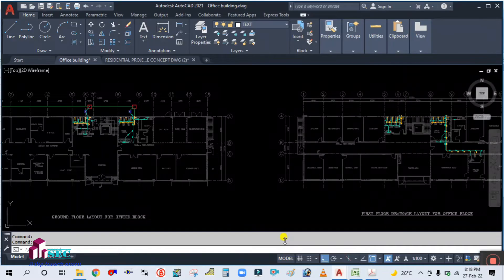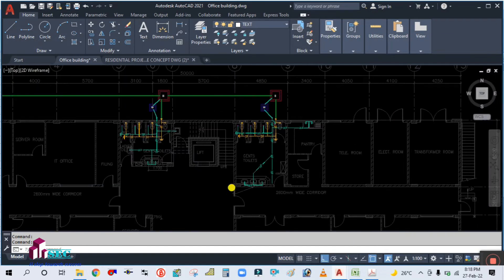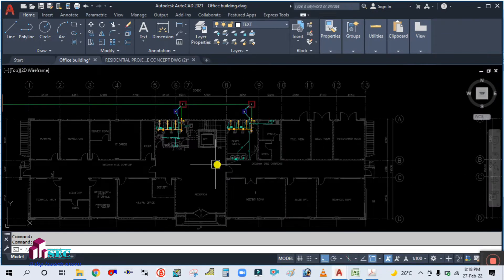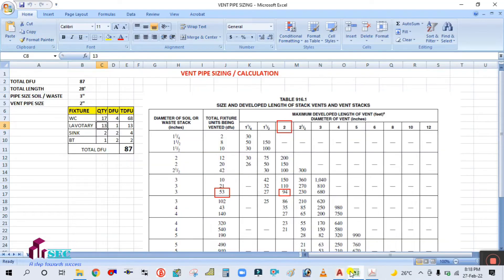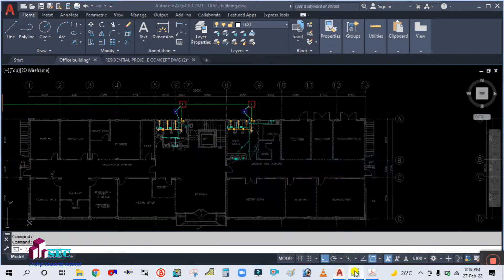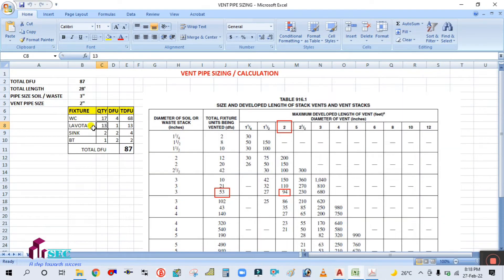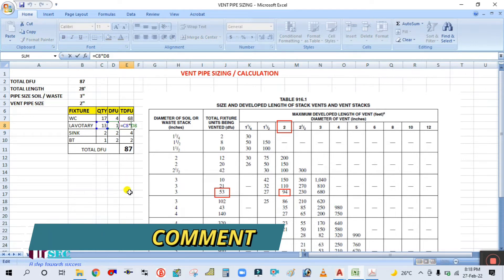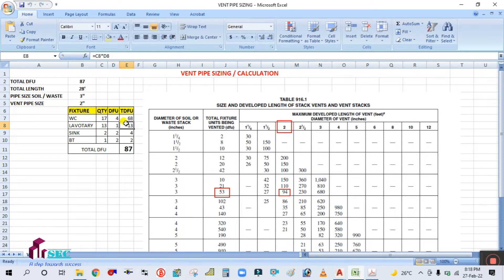Laboratory — in our project the laboratory is nothing but the wash basin. There are 13 total numbers. The drainage fixture unit for the laboratory is 1, so simply multiply: 13 into 1 equals 13. TDFU is nothing but total drainage fixture unit.